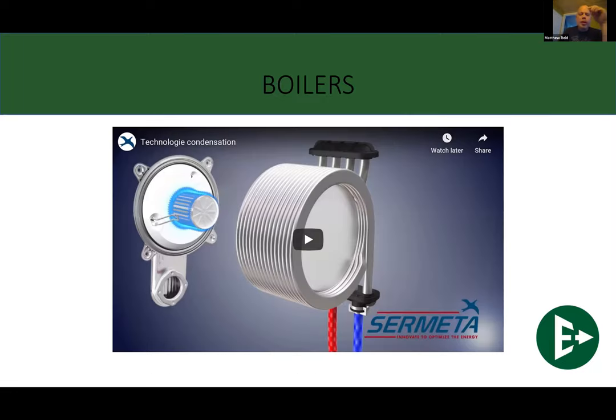Now, the way that this works, you have our burner back here on the burner plate, which mounts into the faceplate of this heat exchanger. It hits the fire plate at the back of that heat exchanger. And one thing to take note of, if you might have seen it in the video, is that it did have its flue gases escaping through in between the stainless steel rings. So for everyone who's taken one of these apart and cleaned it up, you may or may not have actually really gotten in between these fins to clean them, but that is relatively important to making sure that you're getting maximum efficiency out of these types of heat exchangers.